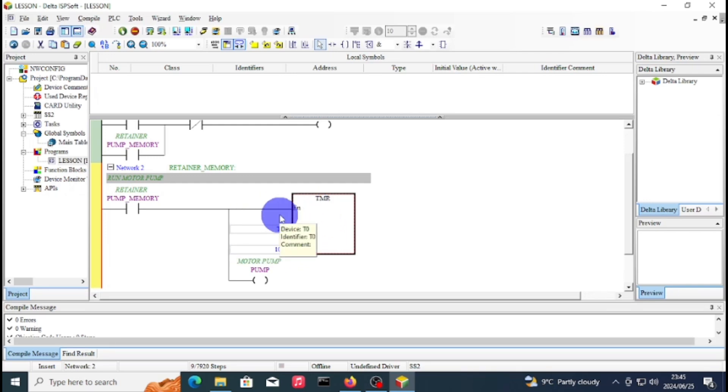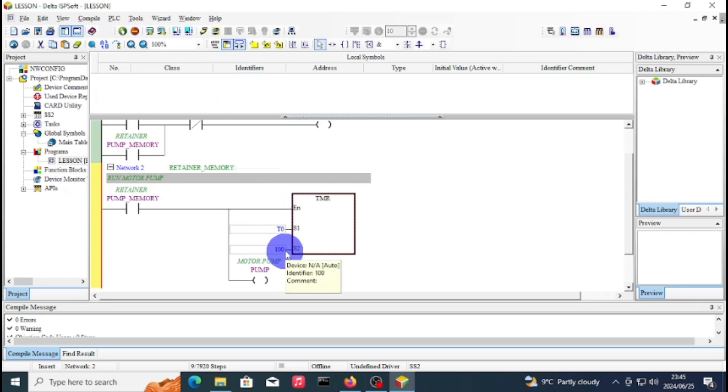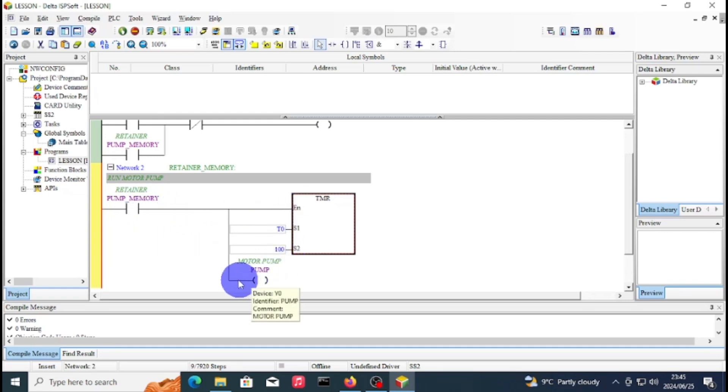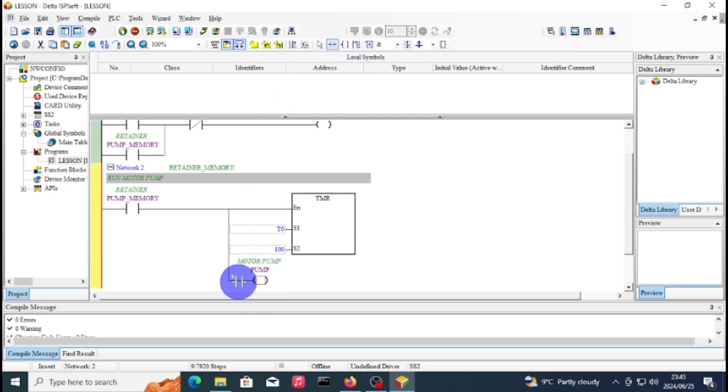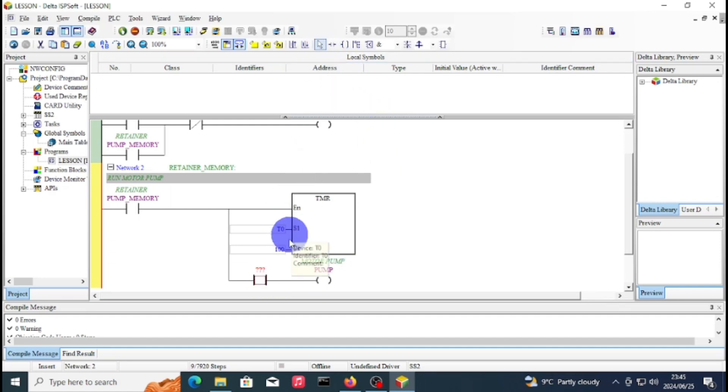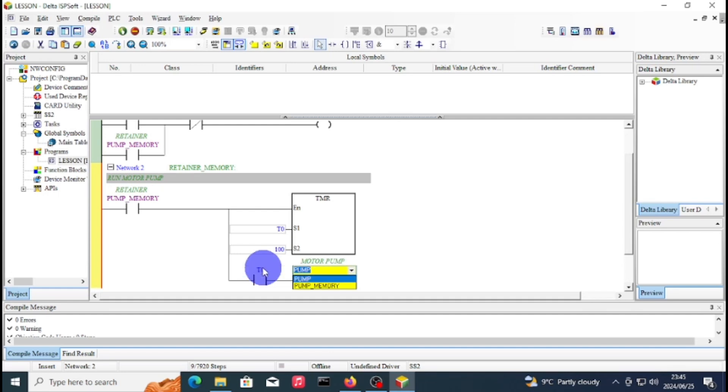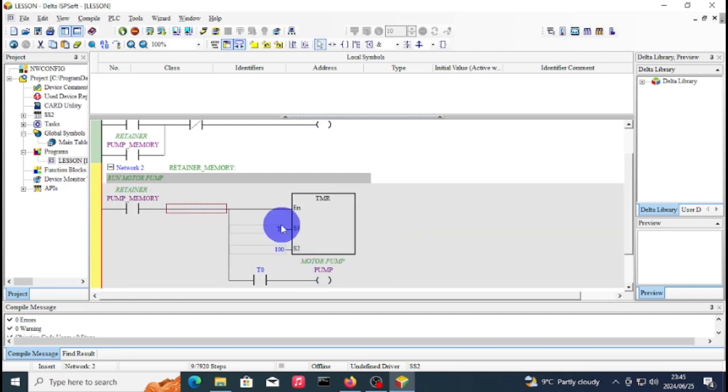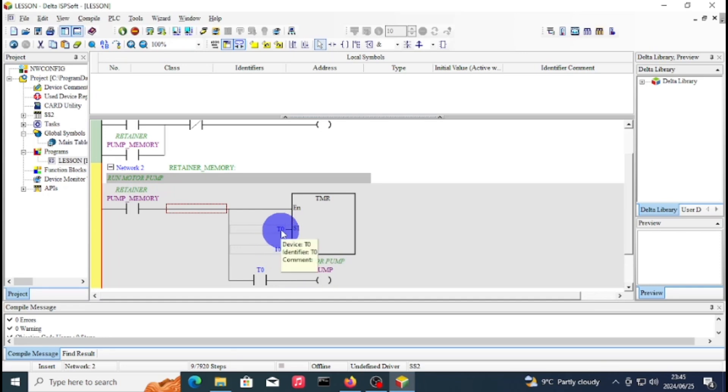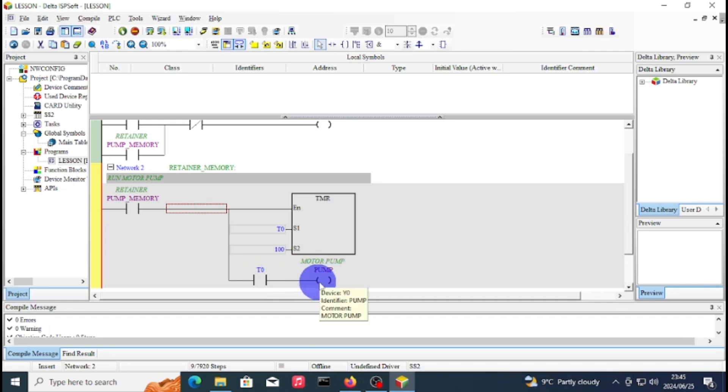This is how you add a timer. When the pump memory is on, the enable will be on, then you start counting. Now you just need to add your contact. We'll start with the on-delay, which will be normally open. As soon as your pump memory starts, the timer will start counting and it will close your T0, and then your pump will run for 10 seconds.